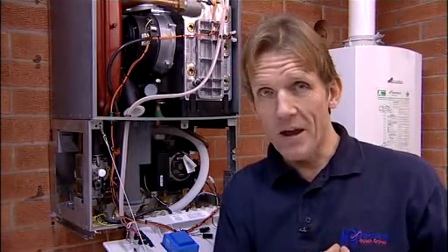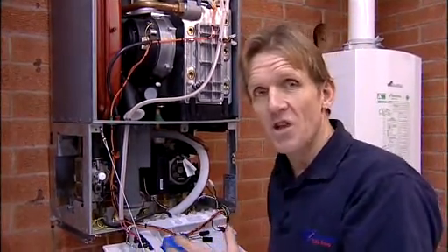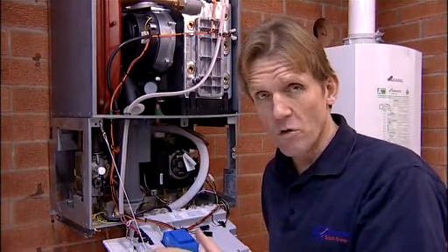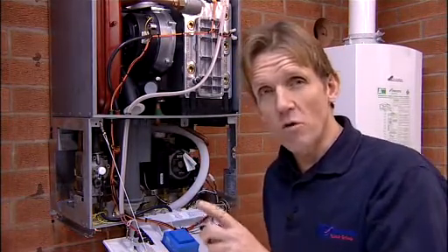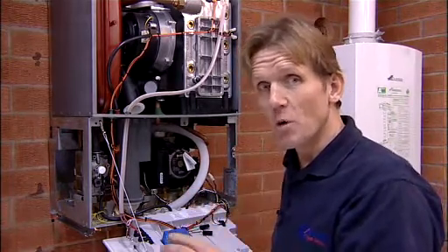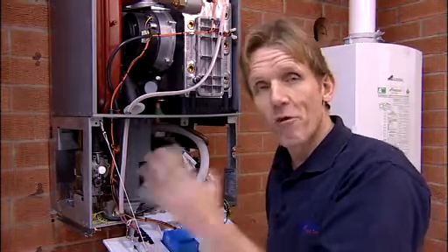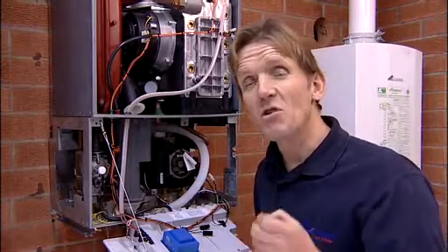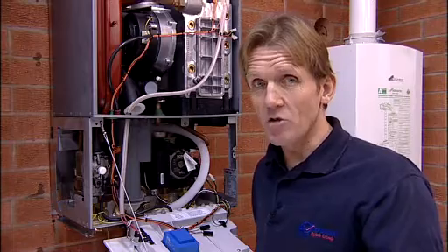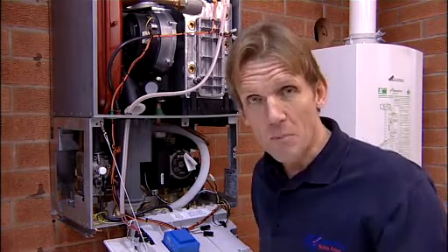The second most common fault is to do with external wiring, and this is how you get the power to the boiler. Now the way the boilers are designed, the power should be fed into the boiler first and then out to the external controls. If you wire up the external controls and then feed the power to the boiler from the external controls, then there can be a situation where the boiler is switched off, but you're still getting a live supply from the external controls to the boiler. Now in certain situations this can be dangerous because the engineer will assume that when he switched the boiler off that the system is powered down.